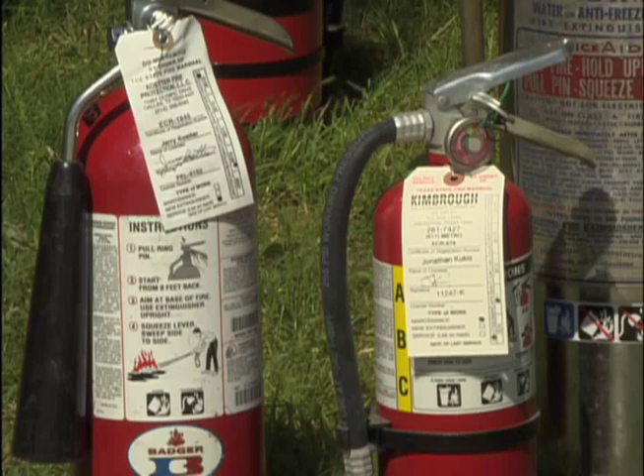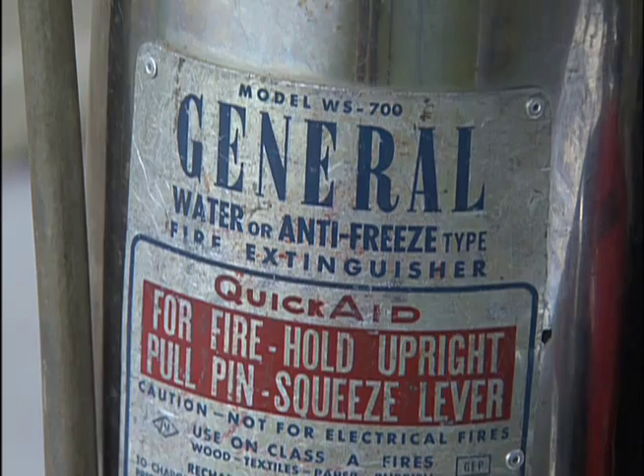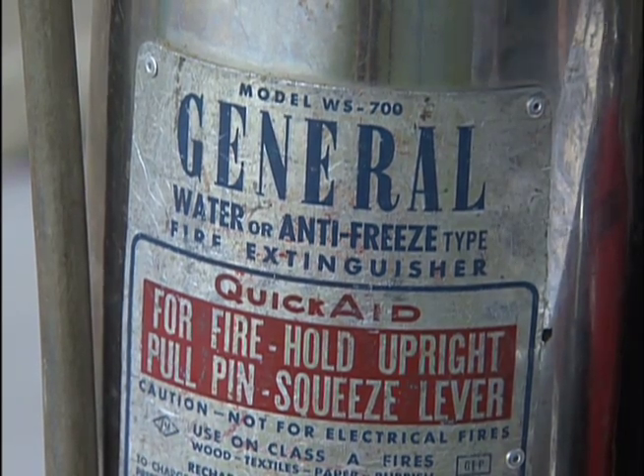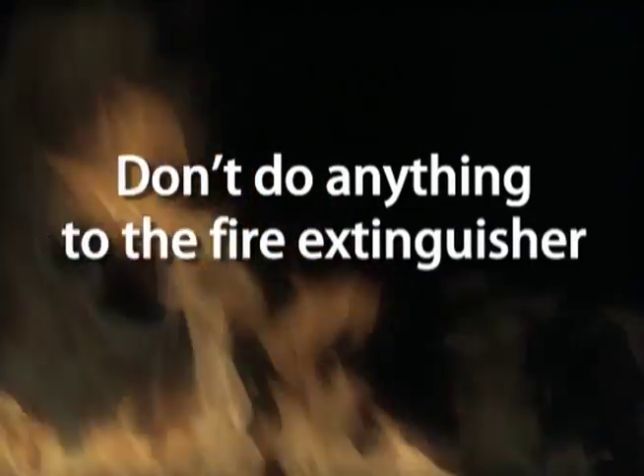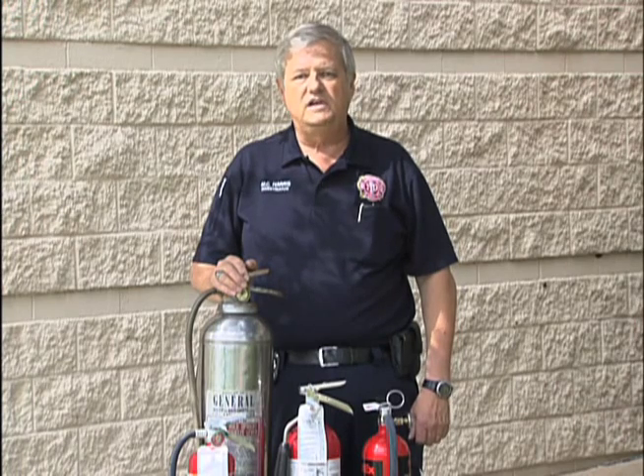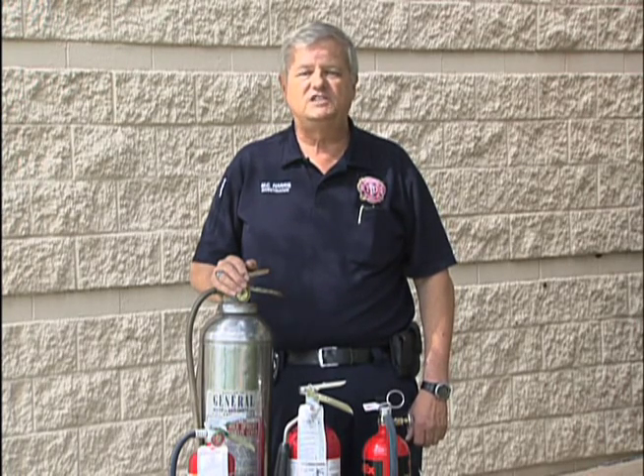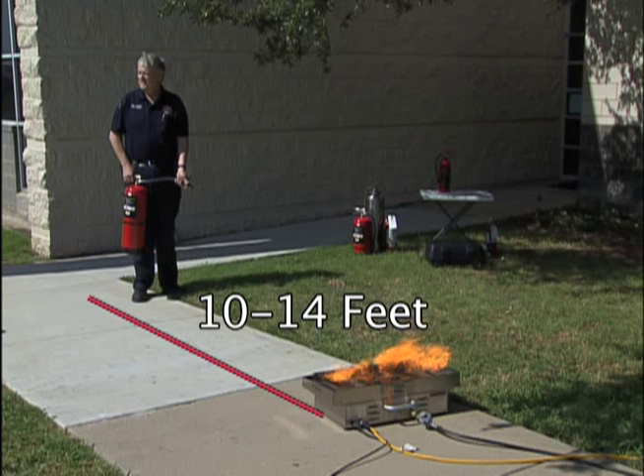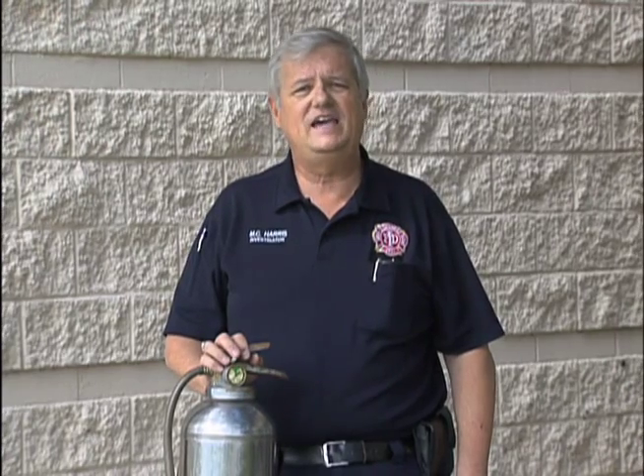Fire extinguishers are designed to be operated only on small fires. A commercial fire extinguisher will usually last only 30 to 60 seconds. Never try and fight a fire that's obviously too big. Always keep an exit to your back and never let the fire get between you and the only way out of the building. Take the fire extinguisher to the fire before you do anything to it. Once you get to the fire, you need to make sure you're at least 10 to 14 feet away from the fire. That's going to keep you safe, and it's going to keep the high pressure of the fire extinguisher from scattering the fire. To remember how to use a fire extinguisher, just remember the word PASS, P-A-S-S.